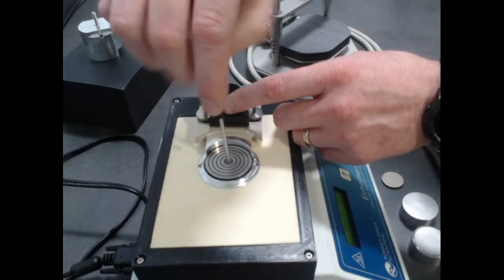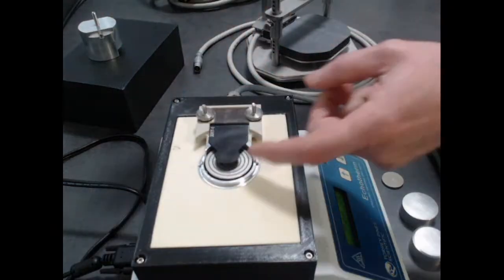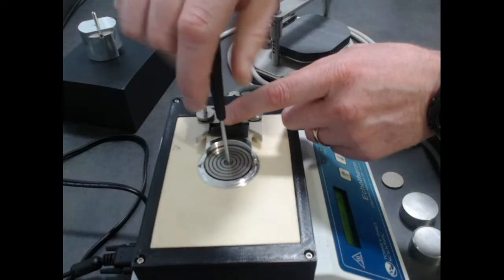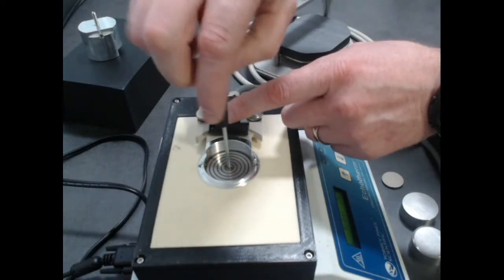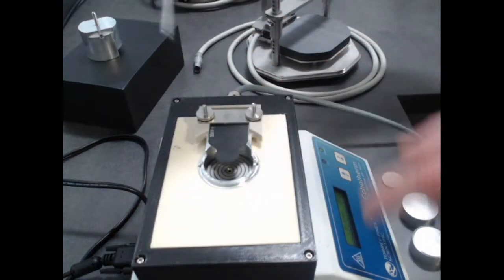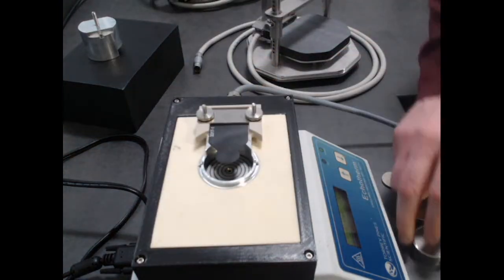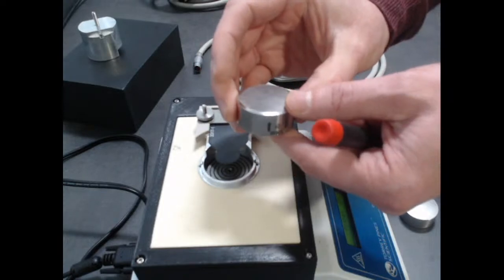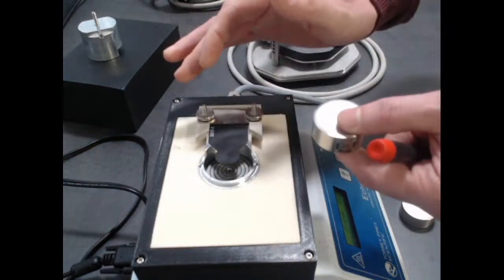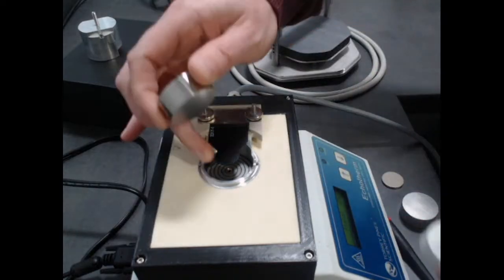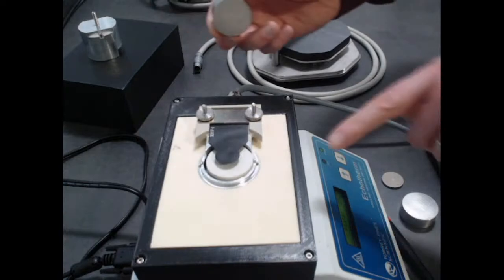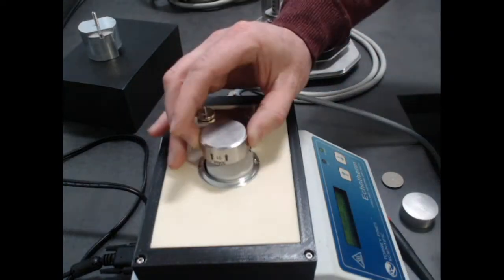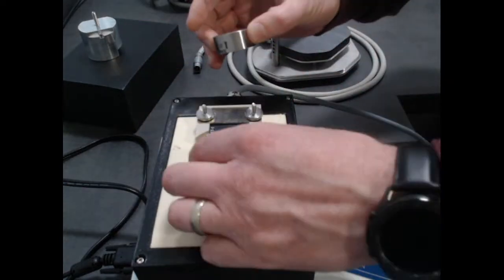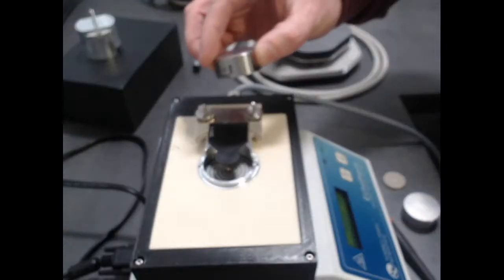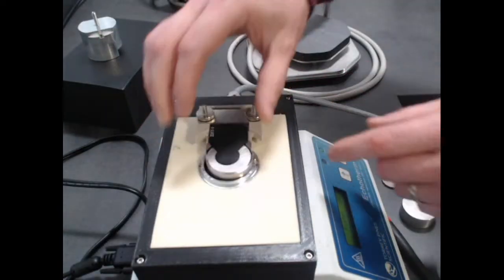So if you have a very thin material, you can raise the floor, and that allows you to test a wide variety of thicknesses. The maximum dimensions for the dry bath setup are 40 millimeters diameter, which is what this sample is, by 20 millimeters in height per half. So per sample half. If it was asymmetric, you would place your known material on the bottom and your unknown on top. That would be a single-sided setup. But we're going to do a symmetric setup where there's a sample on top and bottom.